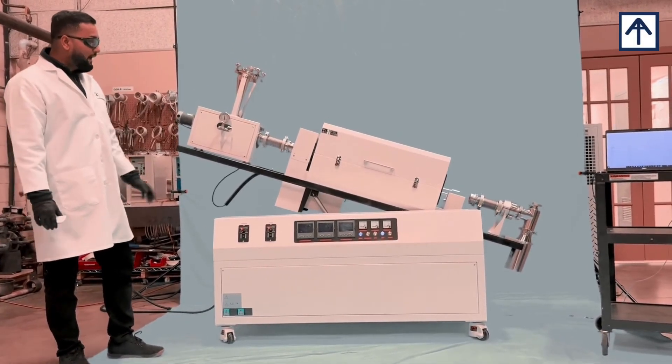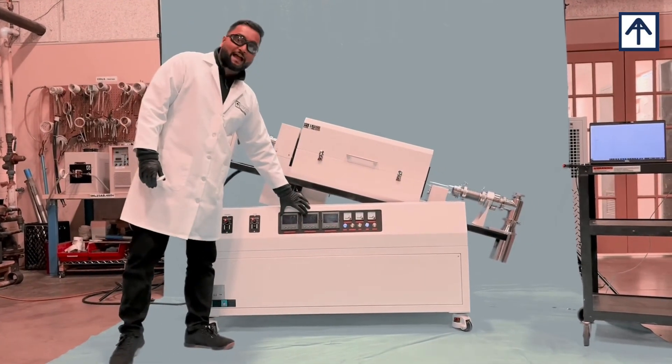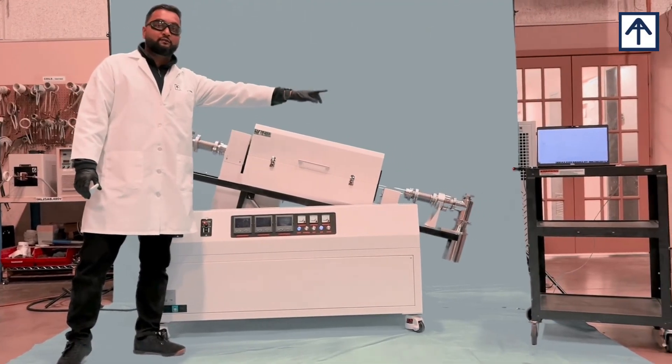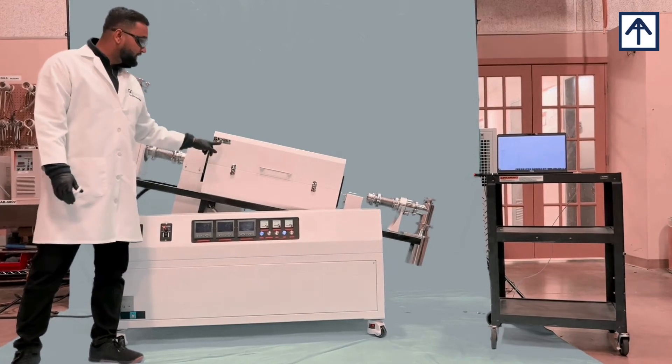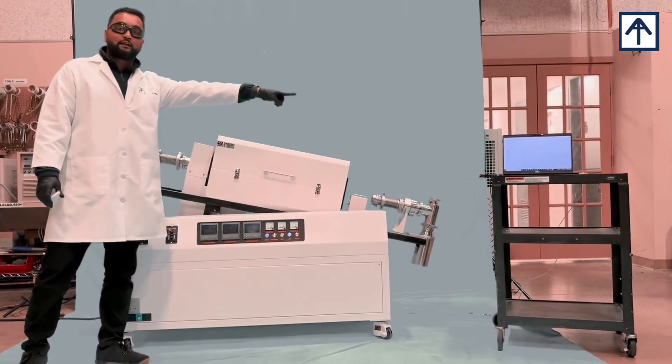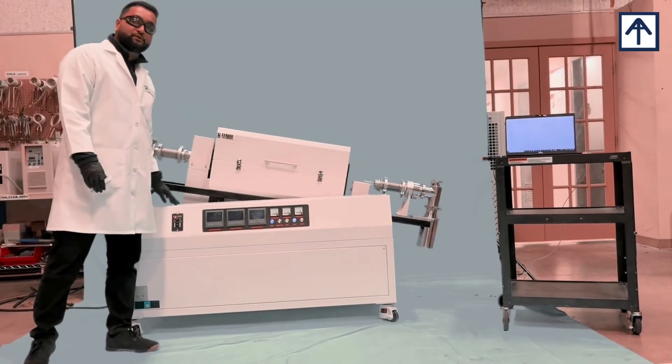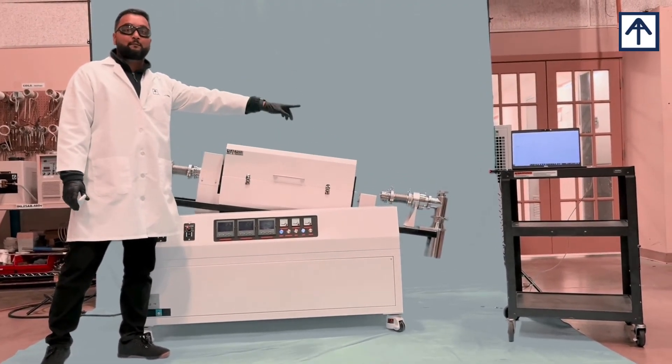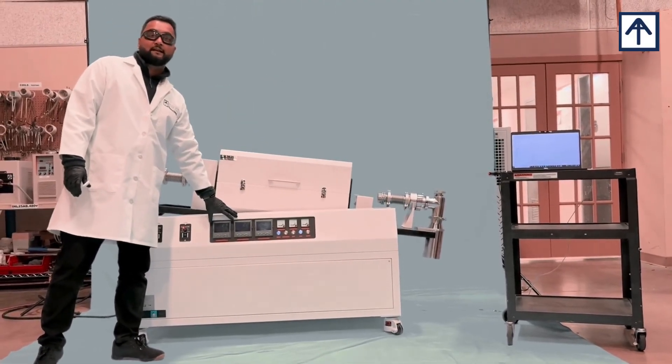As this is coming down, I'll also introduce you to our controllers. Our controllers have the capability of being communicated with computer software while you directly log your data in real-time analysis. There is an individual sensor for each controller. You can collect data in real-time analysis as to what temperatures are working and you can set your programs and program temperature profiles—everything from the main computer interface or manually on the main side.